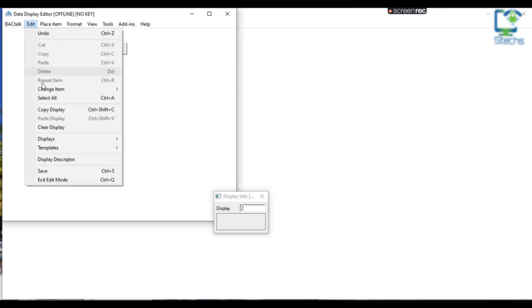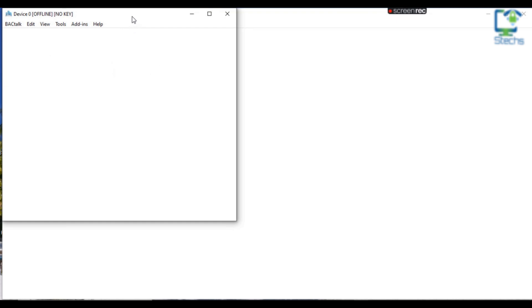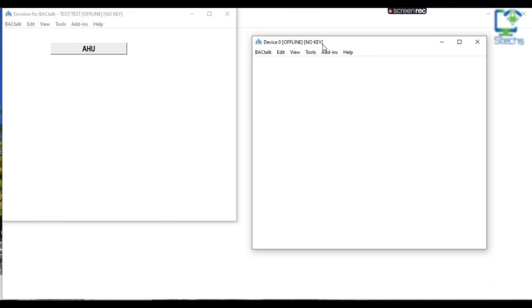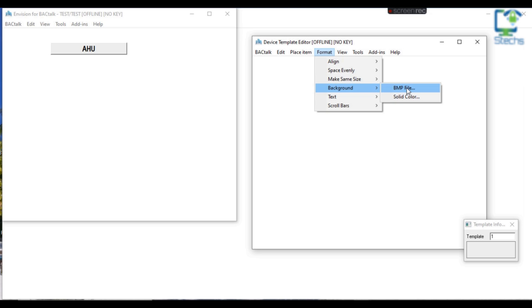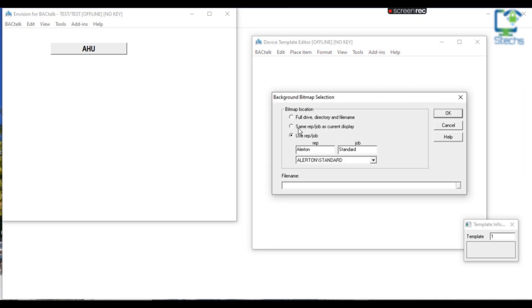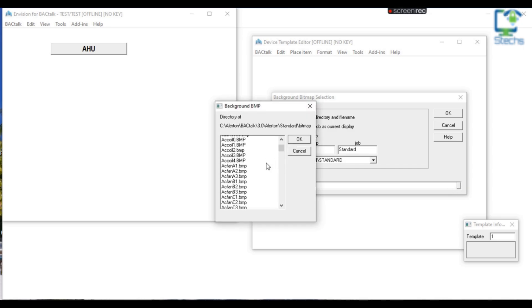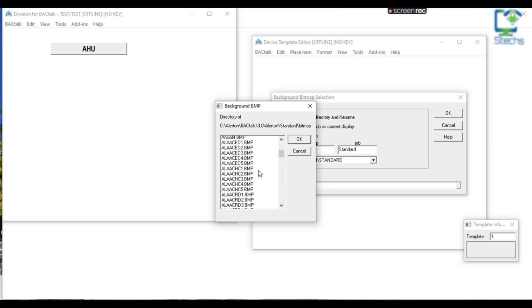Now on the Systems Page we have an AHU button with the connected controller. Double-click on that AHU button to configure the template page designed for the AHU. A new window has opened with device instance 0 selected. Select edit mode from the Edit menu so we can edit the template for AHU graphics. Click on the Format menu in the menu bar, select Background, and click on BMP File. A window opens for background bitmap selection. To use the default library of bitmap images, choose the Rep Job as Alerton and Standard, then choose the file from the File Name selection column.